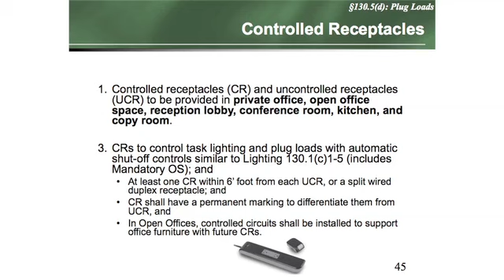So I'll tell you a little story. So WattStopper makes a wonderful product. It's a little tiny strip tap that's got a little personal occupancy sensor on a telco cord. Just plugs right into there. If you're in the area, part of the strip goes live, the other part is always live. So we were completely set up for this until we got here. Plug-in strips that use occupancy sensors shall not be used to meet the code. Why? Because somebody could unplug it. It's a building code. It's got to be permanent, right? So this has got to be a permanent solution. It can't just be a simple little plug-in strip.